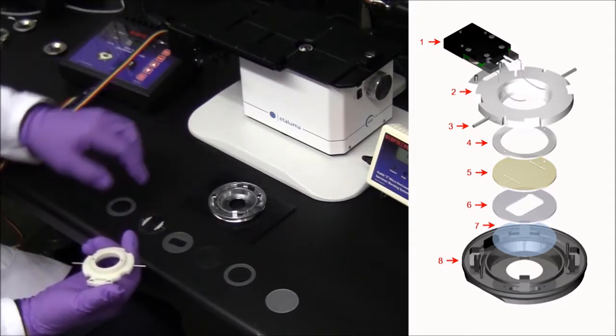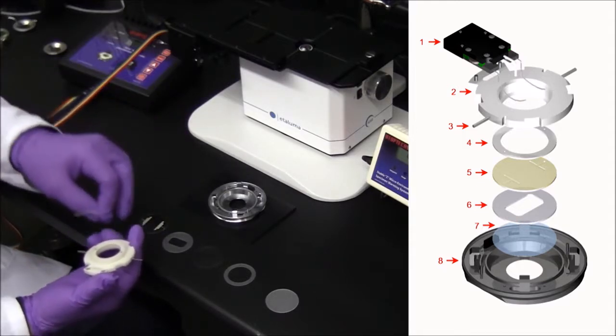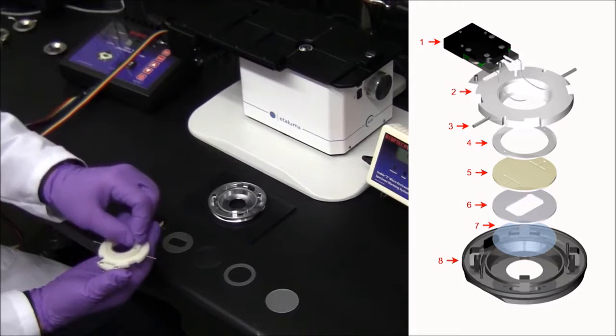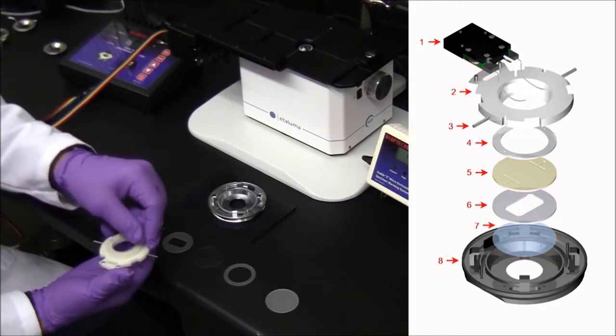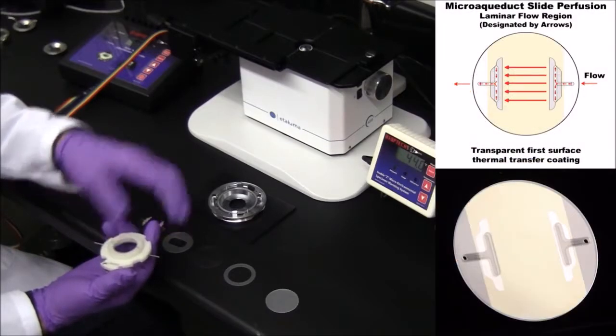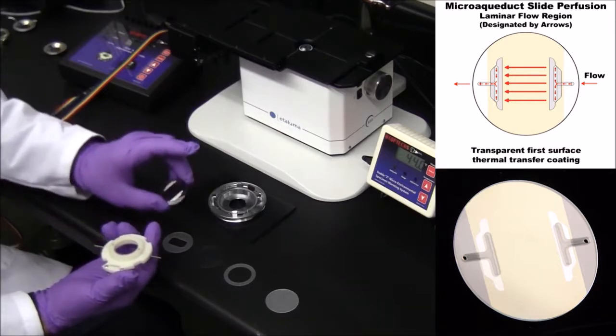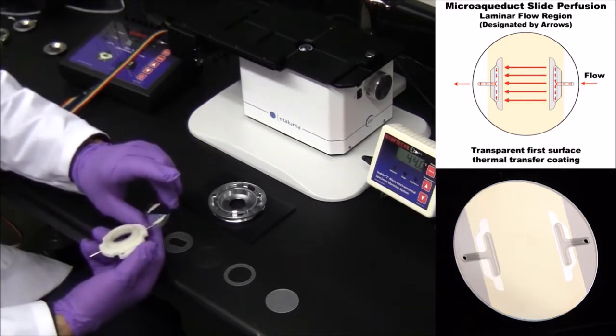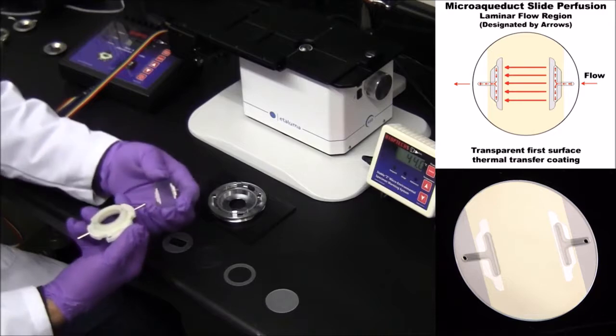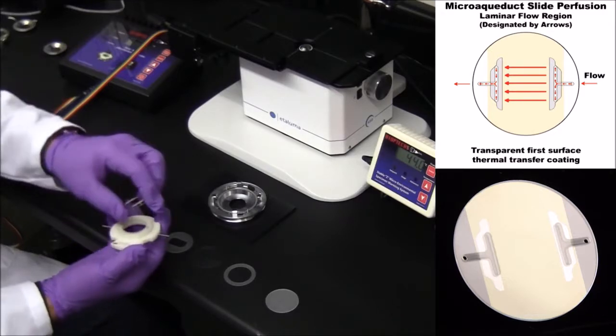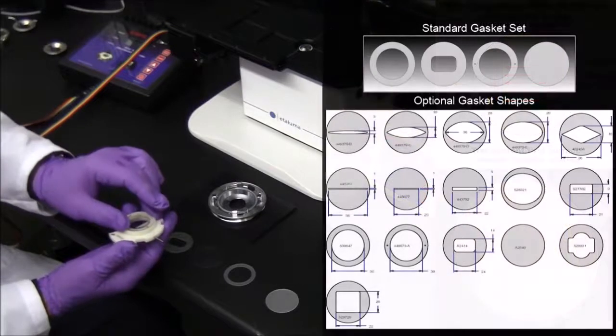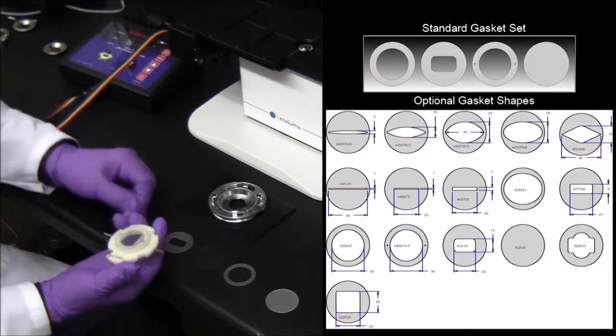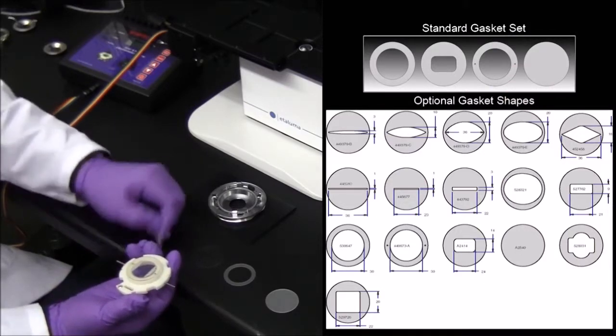When assembling, a gasket is placed on the bottom surface of the top seal of the perfusion flow that passes through the optical cavity. The next component is a microaqueduct slide, the heart of the FCS2. It is a combination of an optical surface, temperature control component, and microfluidic guide having perfusion grooves to allow media to pass through the optical cavity.